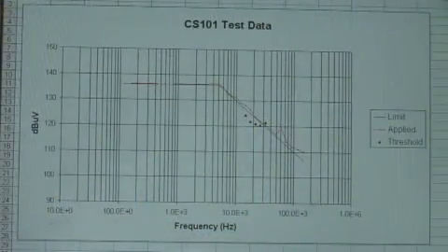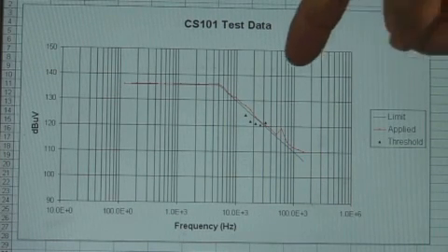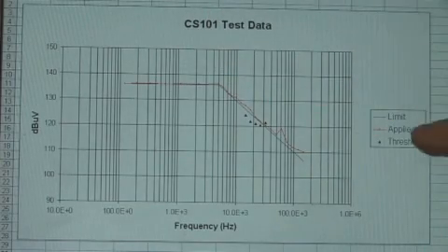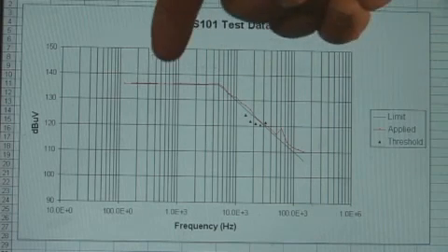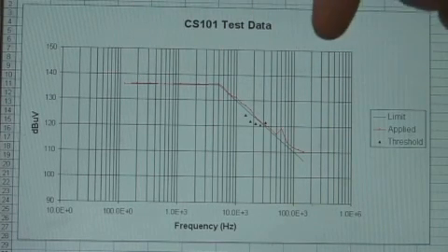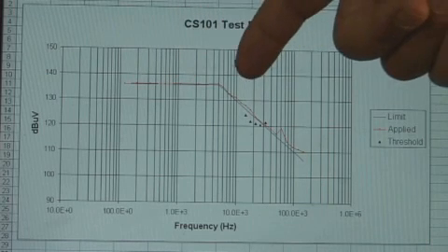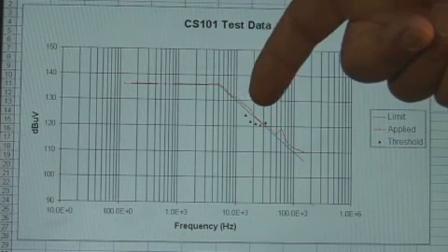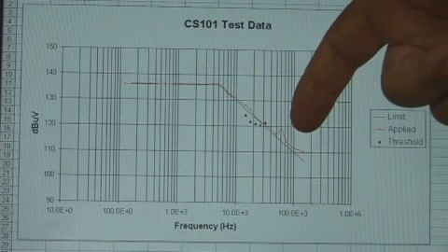With the testing complete, we've now recorded all the measurements, and we have a chart that we particularly like to use for presentation, where the blue line is the limit, and that's following the curve, and there's an applied voltage line which is nearly right on top of the blue line. So we're following just above the limit curve, and as you can see, when I get out into the areas where the slope is, I let the excursions exaggerate a little bit more.